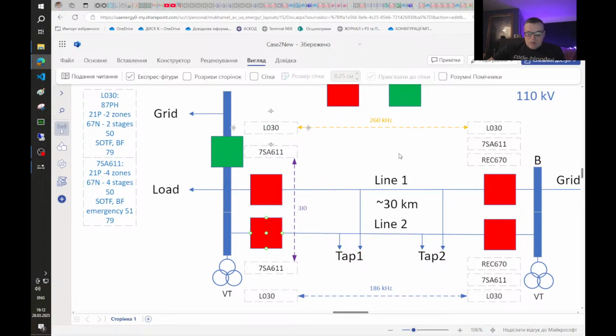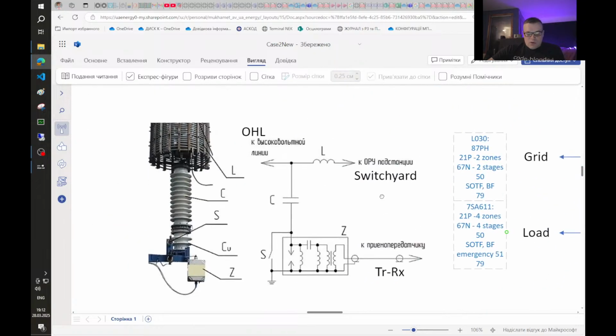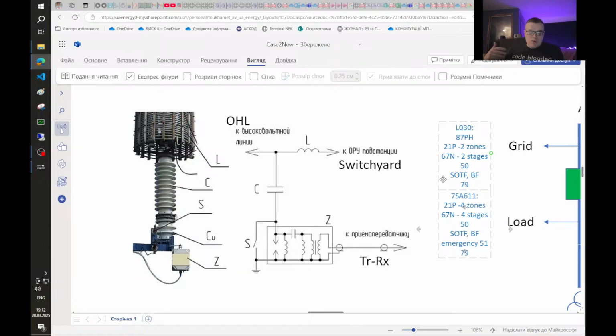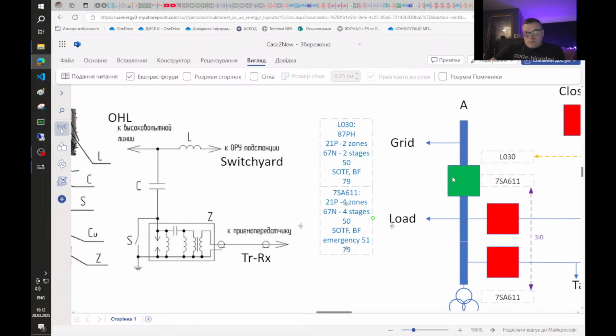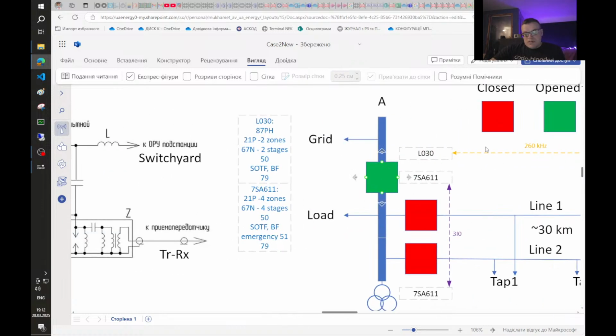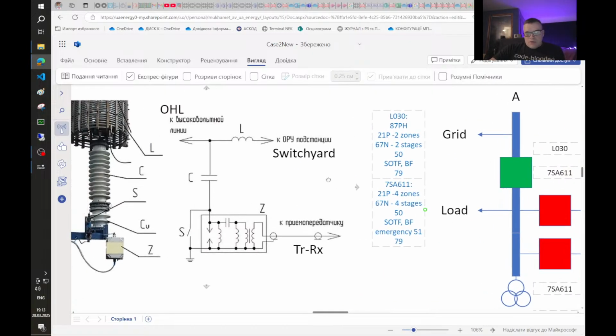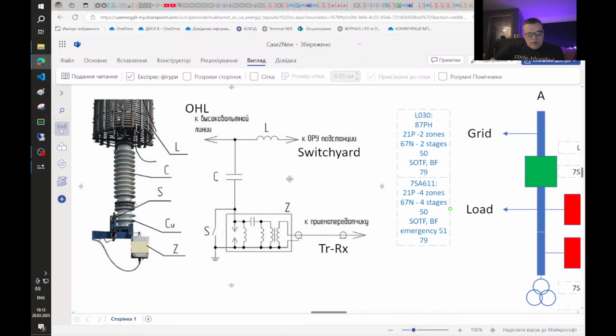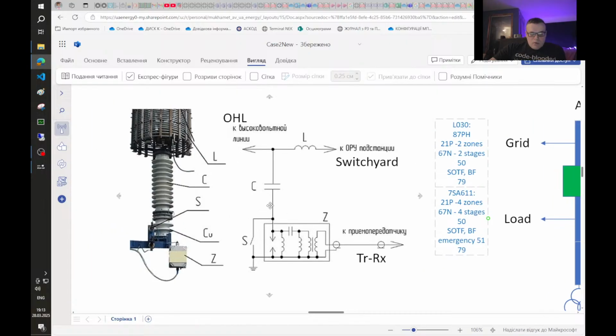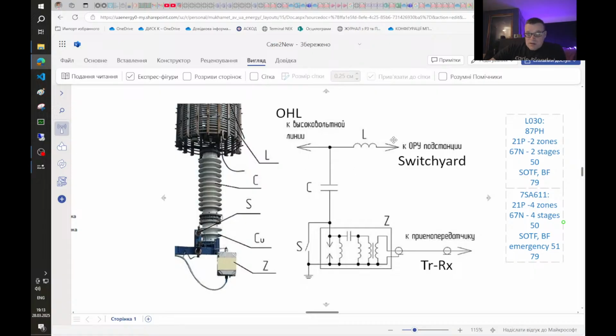Let's talk a bit about high frequency communication channels briefly. Usually for this type of communication, the wires of the line are used, and filters are used to separate high frequency signals from the usual grid frequency. So you can see on this picture this point connected to the switch yard, this connected to the line. This is a low pass filter, and here a band pass filter. In this schematic and picture, you can see how it looks. This band pass filter is connected to the transmitter receiver.